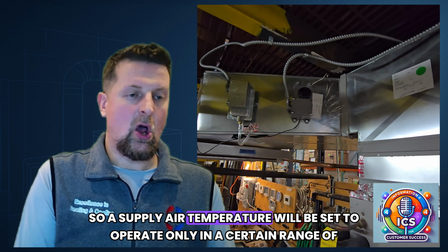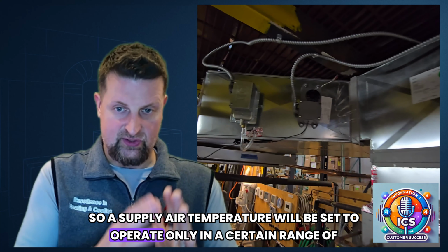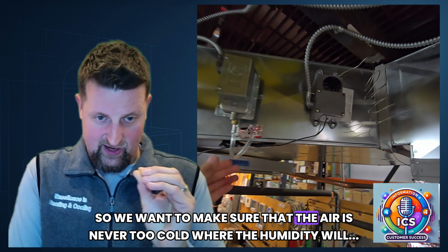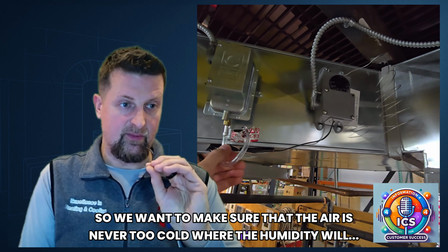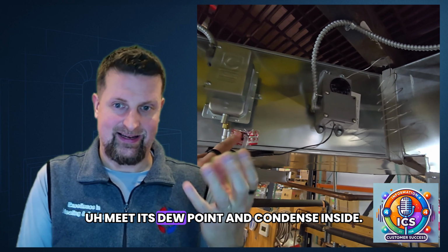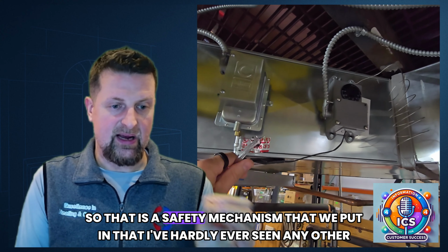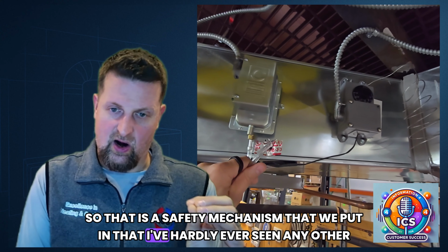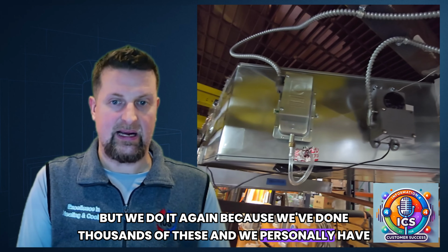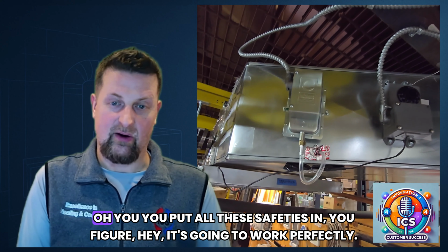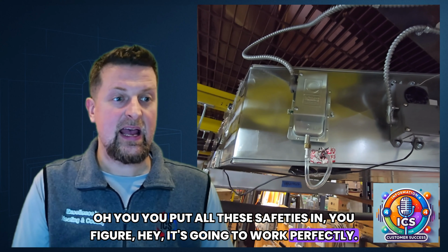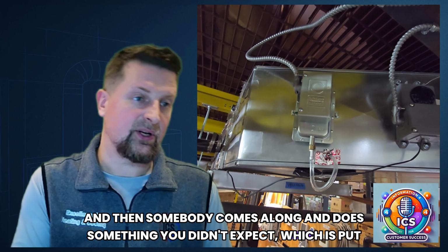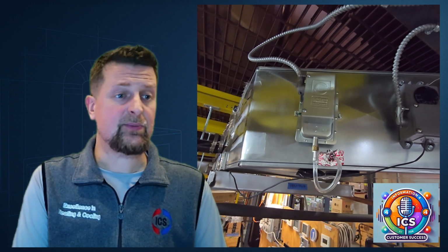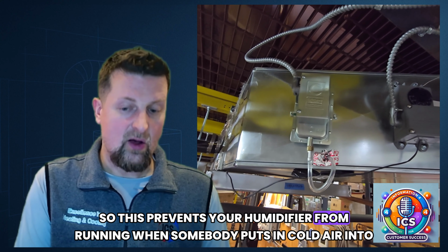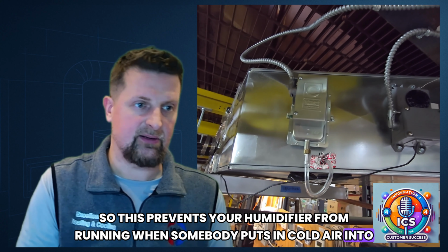So a supply air temperature controller will be set to operate only in a certain range of temperature. So we want to make sure that the air is never too cold where the humidity will meet its dew point and condense inside. So that is a safety mechanism that we put in that I hardly ever see any other contractor do, but we do it again because we've done thousands of these and we personally have made mistakes of not putting stuff like this in. You put all these safeties in, you figure, hey, it's going to work perfectly, and then somebody comes along and does something you didn't expect, which is put air conditioning on in the wintertime. So this prevents your humidifier from running when somebody puts cold air into the system.